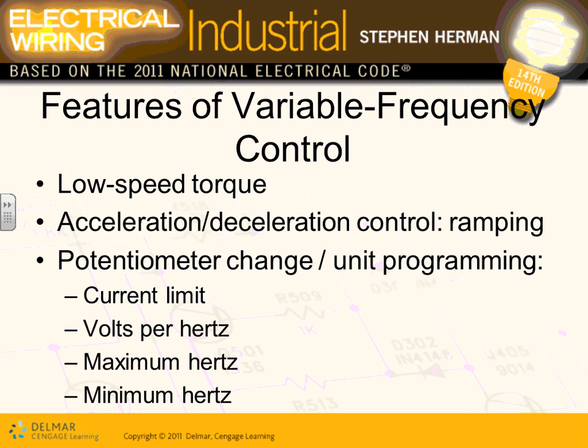It takes your motor and ramps it up, meaning the torque and the current are low, so there's no mechanical or electrical stress in your system, and it makes it run at its speed. Then when you want to turn it off, it ramps it down, so it also reduces the mechanical and electrical stress on the machines and electrical equipment. So these two are called soft start. But the VFD can also speed control the motor: reverse, forward, speed control, ramp up, ramp down, as good as you can get in terms of a motor.